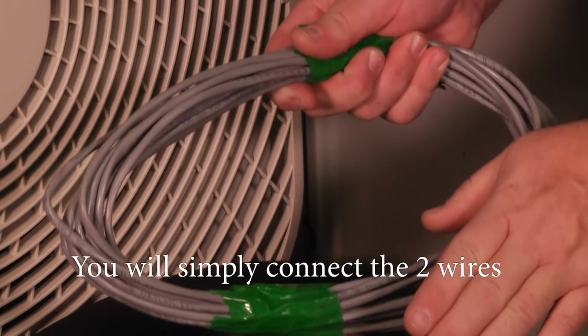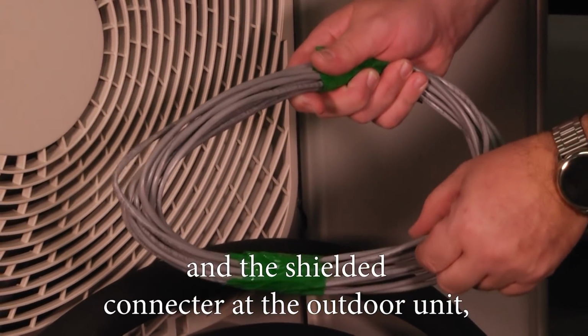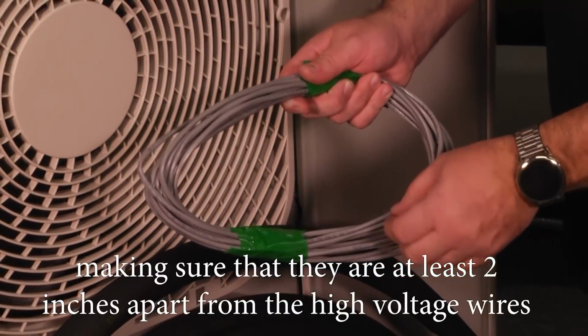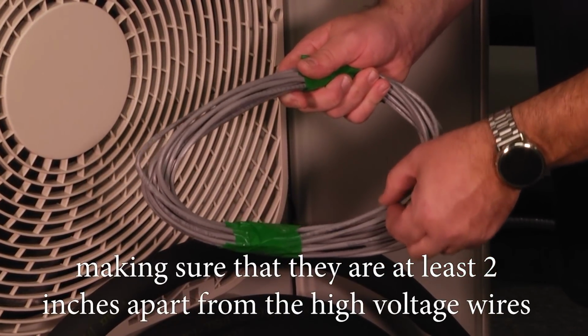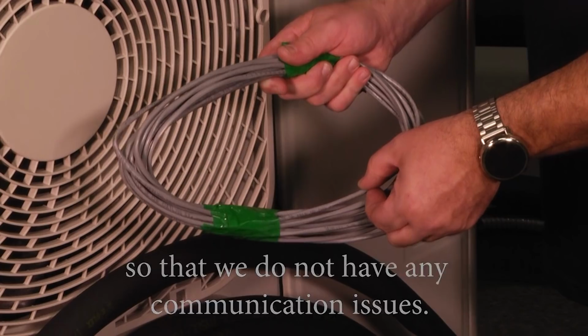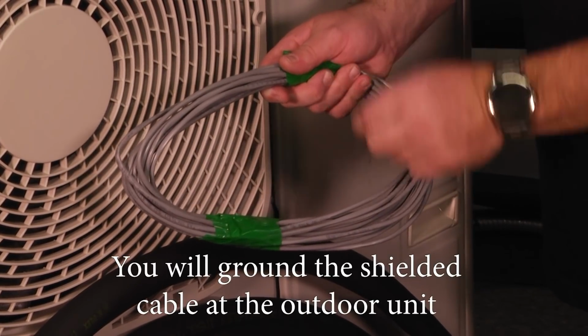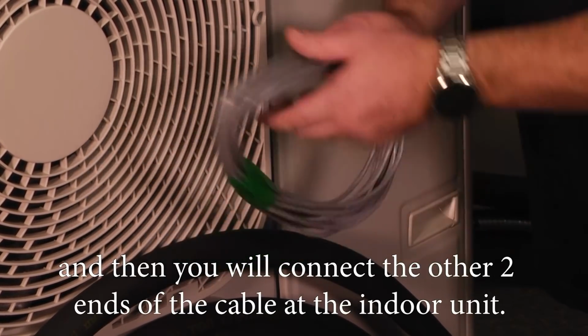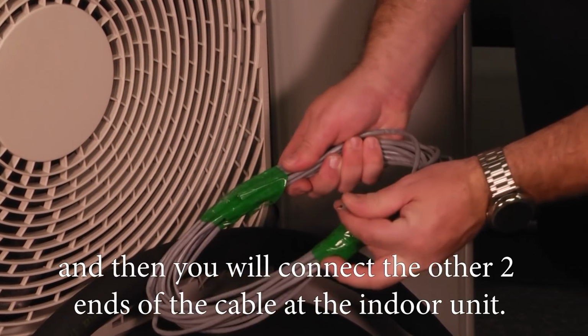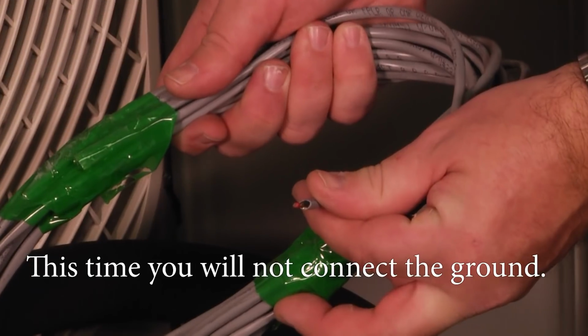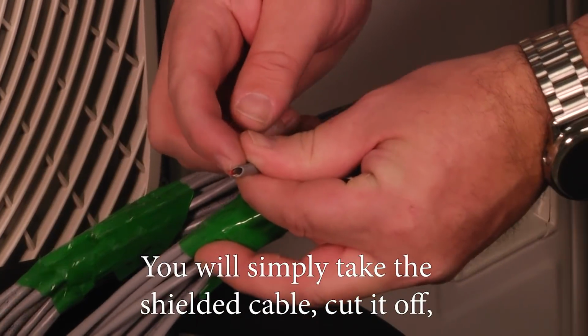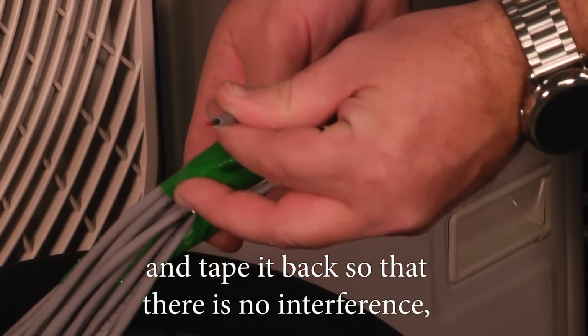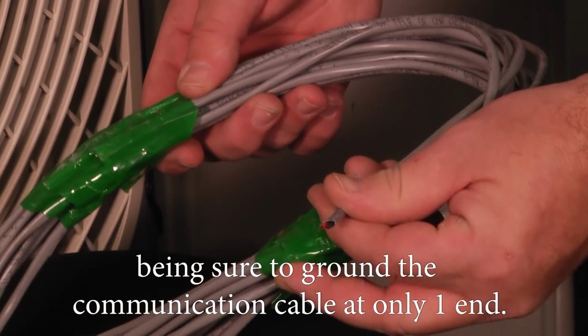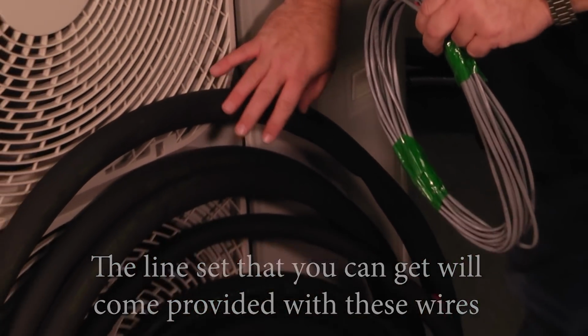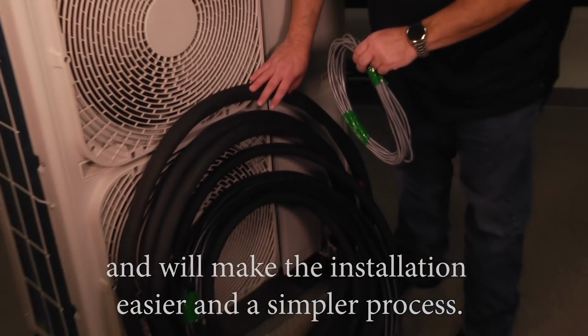You'll simply connect the 2 wires and the shielded connector at the outdoor unit, making sure that they are at least 2 inches apart from the high voltage wire so we don't have any communication issues. You'll ground the shielded cable at the outdoor unit, and then you'll connect the other 2 ends of the cable at the indoor unit. This time you will not connect the ground. You'll simply take the shielded cable, cut it off, and tape it back so that there's no interference, being sure to ground the communication cable at only one end. The line set that you can get will come provided with these wires, and it'll make the installation easier and a simpler process. Thank you.